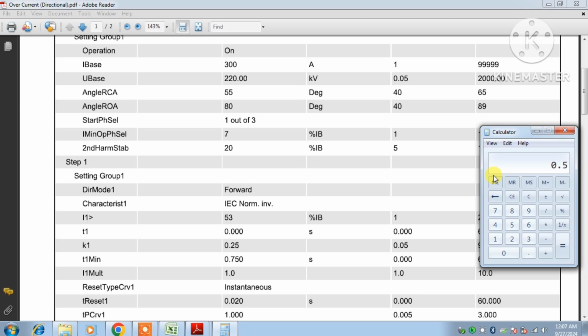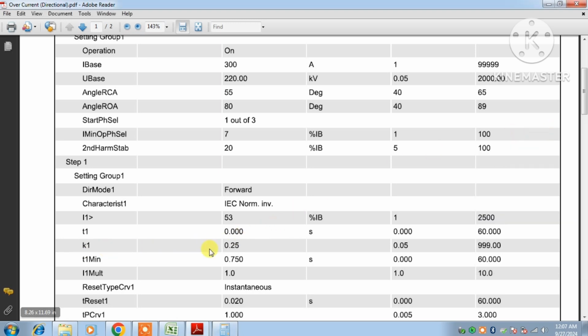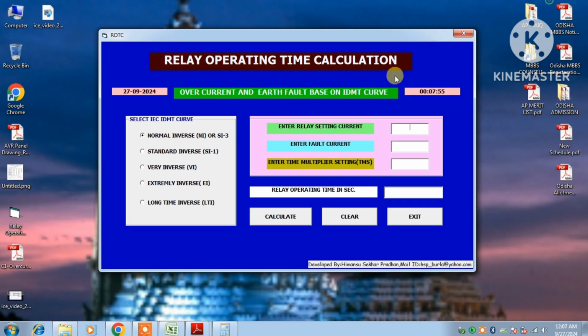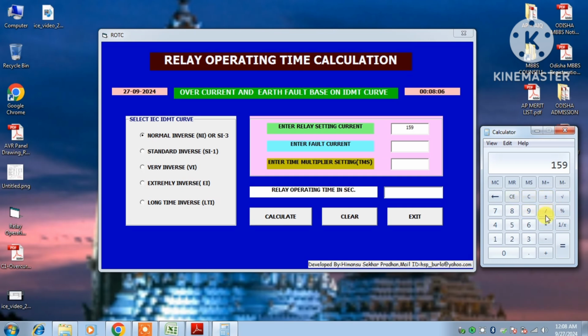So if you calculate, 0.53 into 300 is equal to 159 amps. This is the TMS, the time multiplier setting, given as 0.25. So now we will go to the application. Like this, the setting current is 159, and suppose we take the fault current as 5 times, so 5 times 159 is 795 amps. The TMS is given as 0.25.